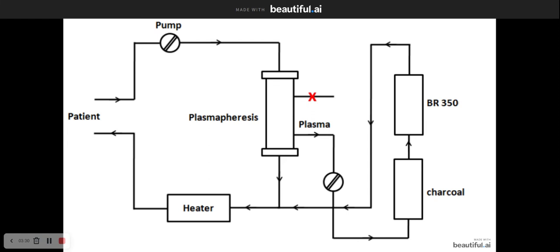A negative pressure is applied via the effluent pump to remove plasma from the blood side of the membrane to speed up the process. Separated plasma then passes through a cartridge containing charcoal particles which absorb lipid-soluble toxins.